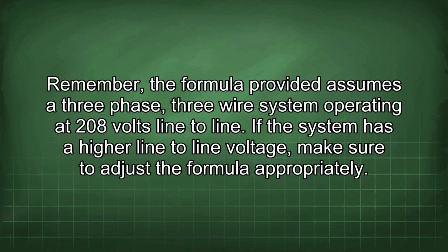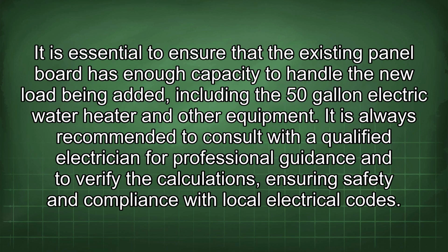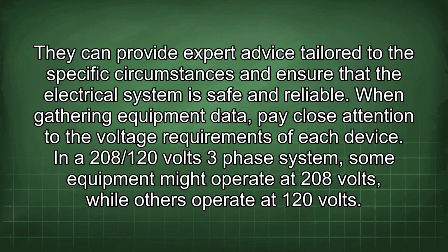Remember, the formula provided assumes a three-phase, three-wire system operating at 208 volts line-to-line. If the system has a higher line-to-line voltage, make sure to adjust the formula appropriately. It is essential to ensure that the existing panel board has enough capacity to handle the new load being added, including the 50-gallon electric water heater and other equipment. It is always recommended to consult with a qualified electrician for professional guidance and to verify the calculations, ensuring safety and compliance with local electrical codes. They can provide expert advice tailored to the specific circumstances and ensure that the electrical system is safe and reliable.